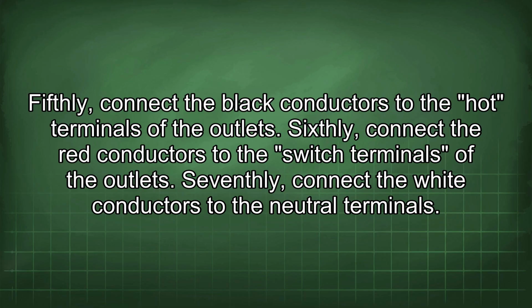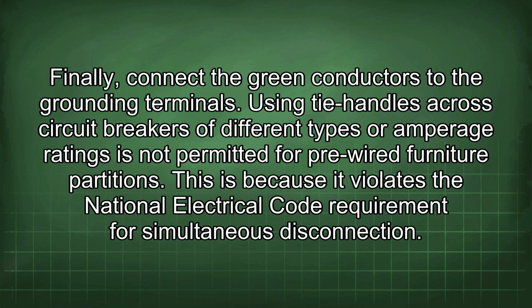Fifthly, connect the black conductors to the hot terminals of the outlets. Sixthly, connect the red conductors to the switch terminals of the outlets. Seventhly, connect the white conductors to the neutral terminals. Finally, connect the green conductors to the grounding terminals.